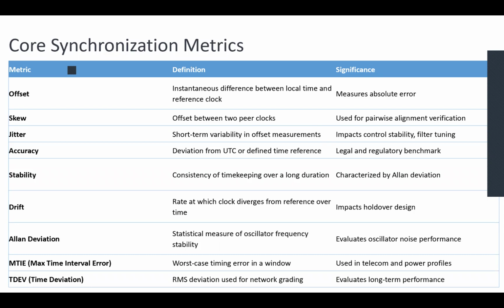Jitter is another parameter that we have to audit to make sure the synchronization is validated and verifiable. It's the short-term variability in offset measurement, which impacts the control stability or filter tuning. Now, accuracy is the deviation from UTC or a defined time reference, which is basically a legal and regulatory benchmark. Accuracy is quite understandable because we cannot have zero error in any system. It's a physical system, so accuracy defines how far we deviate from our central time unit.